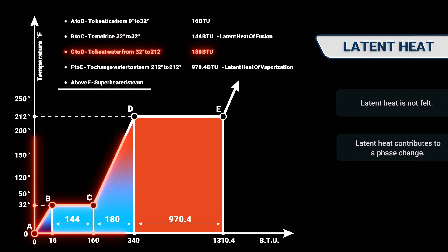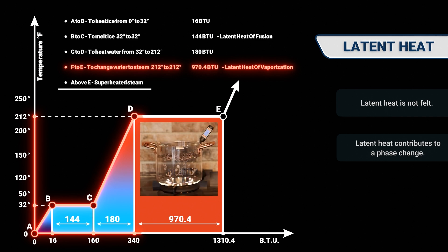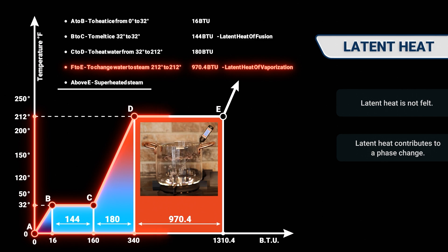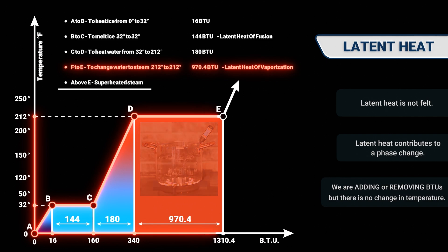The amount of heat it takes to change a solid to liquid and vice versa is called the latent heat of fusion. For water, that's about 144 BTUs per pound. It's latent heat because it's hidden heat. We're adding or removing BTUs, but we're not seeing a change in temperature. The amount of heat it takes to change from a liquid to a vapor and vice versa is called the latent heat of vaporization.